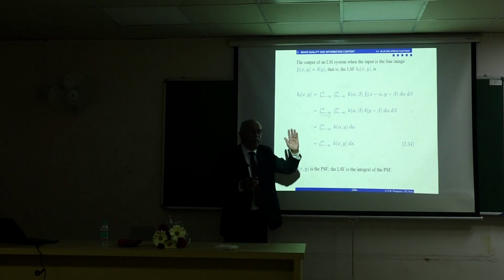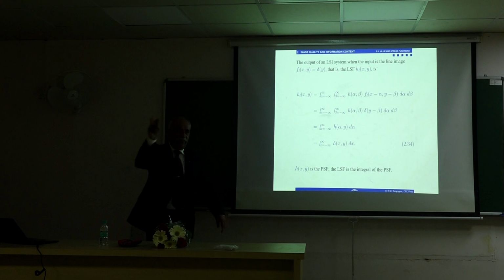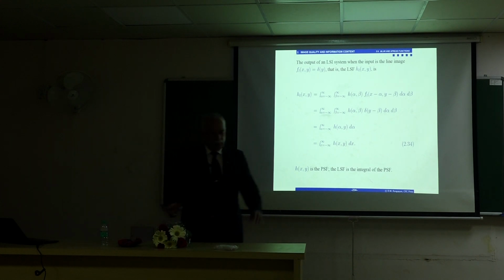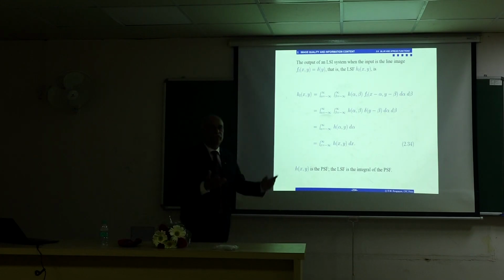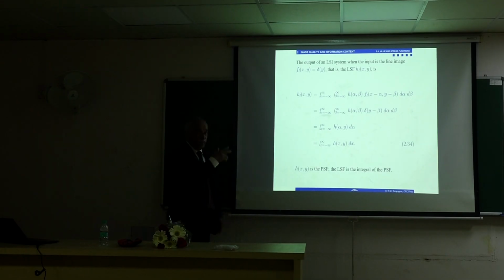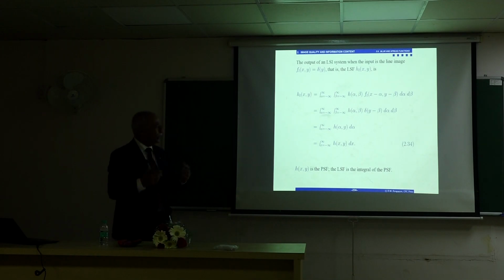So if you can do this at various angles, you can capture line spreads at various angles. So you place your edge at different angles and obtain multiple images and take this, get the line spread. Or if you have a tube, a line function, place it at different angles, take multiple pictures and combine them. Put them in a reconstruction algorithm that we will not be seeing. It's in a different chapter, but go through a reconstruction algorithm, then you can get the point spread function.